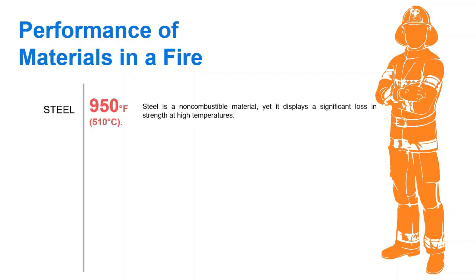Steel. Steel is a non-combustible material, yet it displays a significant loss in strength at high temperatures. Structural steel loses about half of its strength at a temperature of about 950 degrees Fahrenheit or 510 degrees Celsius. At temperatures of about 1350 degrees Fahrenheit or 730 degrees Celsius, steel loses about 90% of its strength.